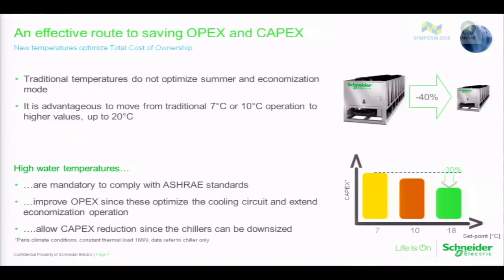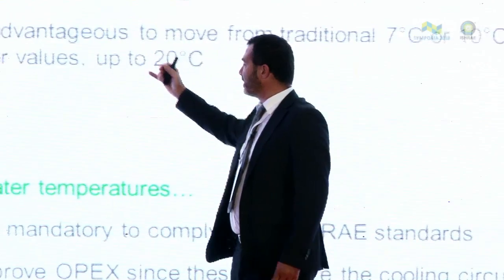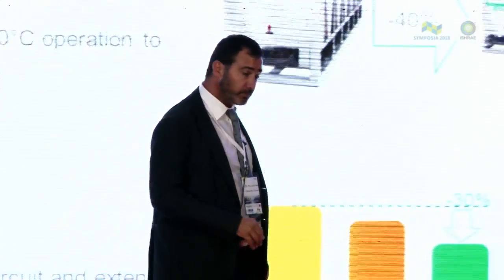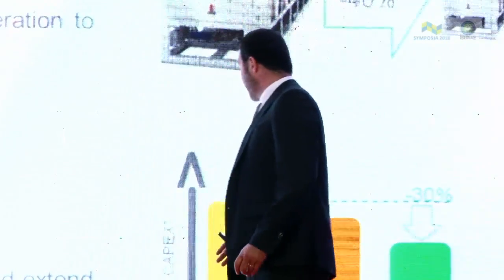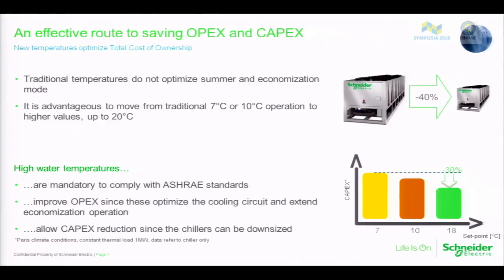So the more we are able to move the design up to 20, the more we are able to increase the power of the chiller. So decrease the footprint, decrease the electrical infrastructure because the compressors are smaller, and therefore the electrical distribution is designed for less amperage. The genset could be downsized and so on. And the more the chiller is efficient, the more we work on the CapEx and on the OpEx.